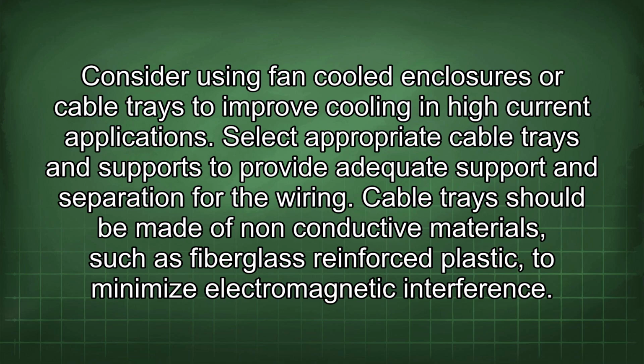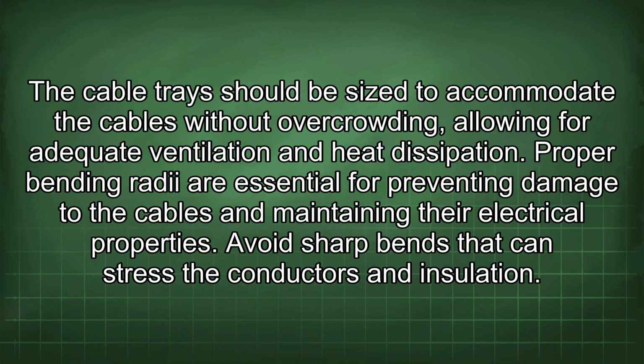Select appropriate cable trays and supports to provide adequate support and separation for the wiring. Cable trays should be made of non-conductive materials such as fiberglass reinforced plastic to minimize electromagnetic interference. The cable tray should be sized to accommodate the cables without overcrowding, allowing for adequate ventilation and heat dissipation.